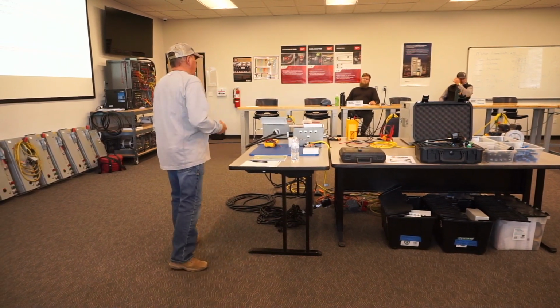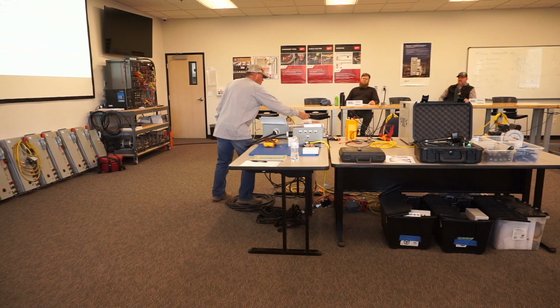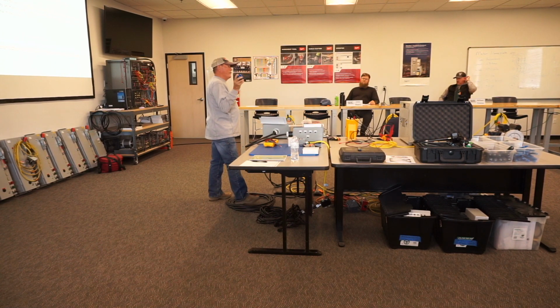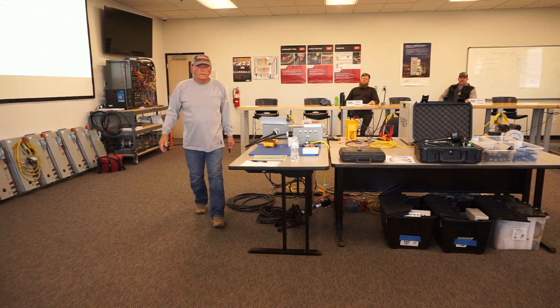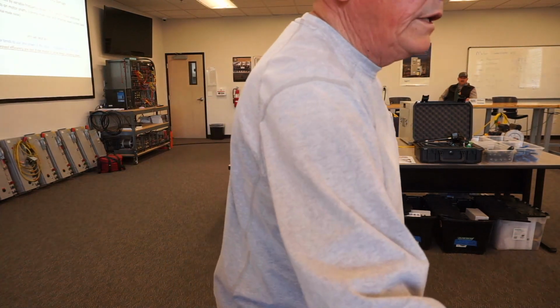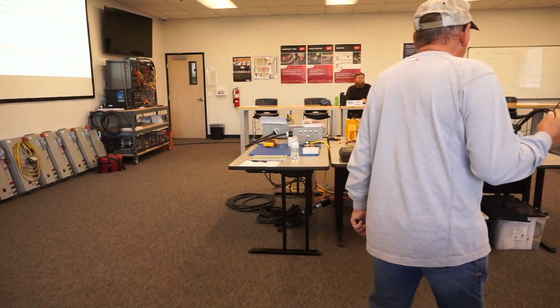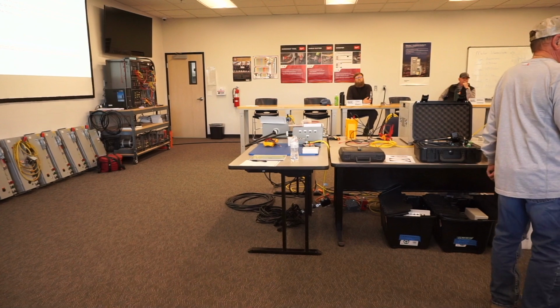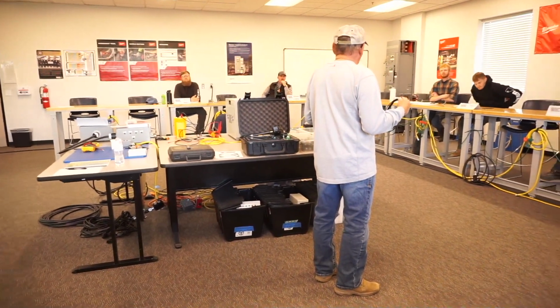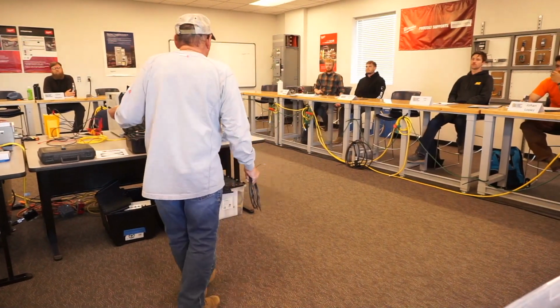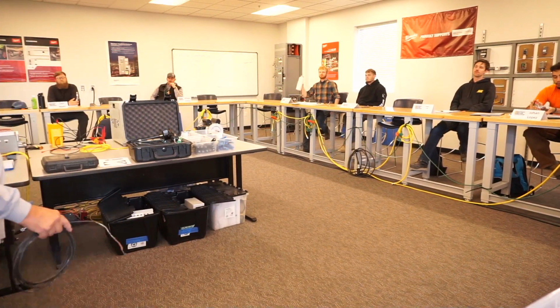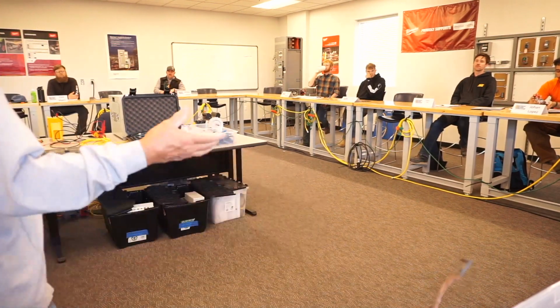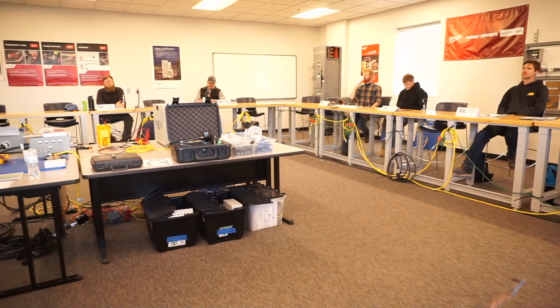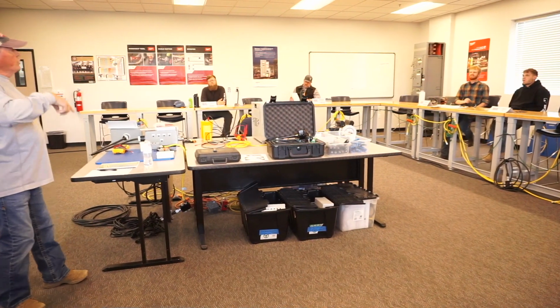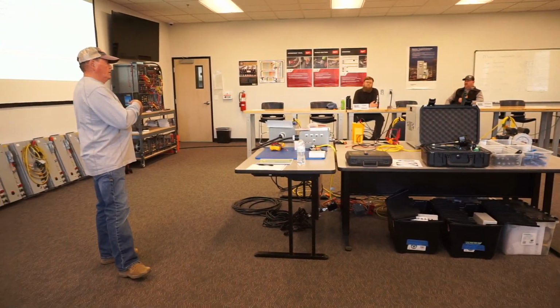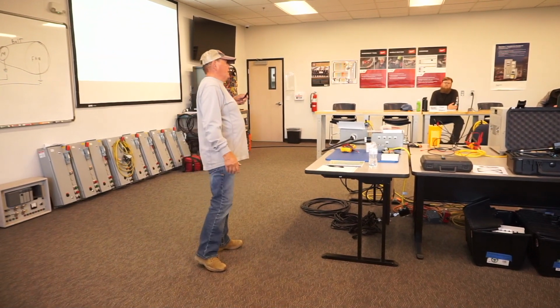So I bought me a kit, and my goal is to put one of these on a solar inverter where, as you saw, I'm losing wire, AC contactors, AC disconnects, fuse holders. It's melting this stuff. And it has to be, in my opinion, the high frequency of the IGBTs converting DC to AC, because I don't know what else it is. So I'm going to try one of these and see if it can dissipate it, because I saw that switching frequency on the DC bus with my scope. I saw it on the AC bus. I didn't think that it would travel through to the DC bus, but it did.